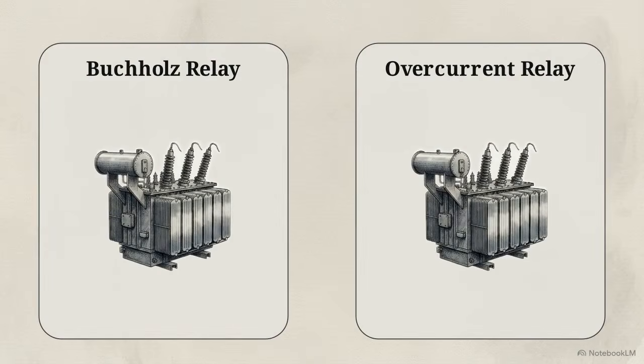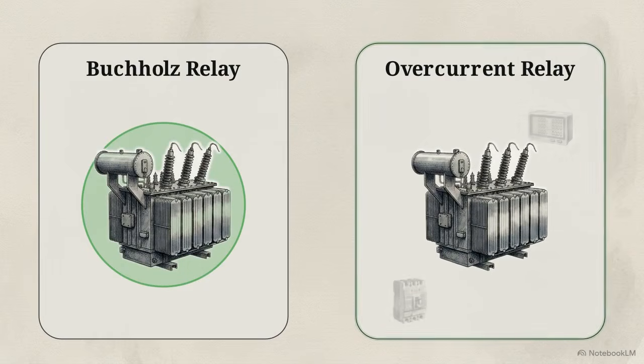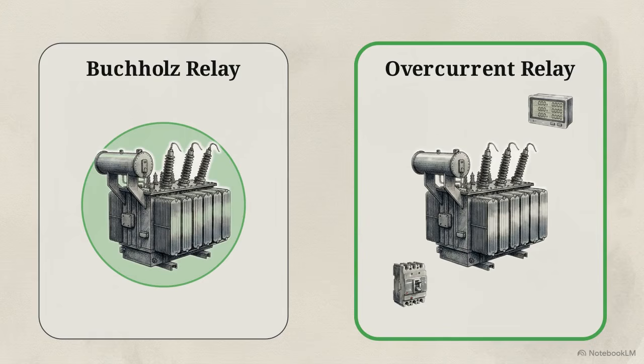This matrix compares the operational envelopes of both systems. The Buchholz relay offers high sensitivity for internal faults, while the overcurrent relay offers broad, system-wide protection with low sensitivity to internal issues. Because the overcurrent relay requires that 150% safety margin, there is a massive gap in its defense. It is mathematically blind to the low-level, smoldering internal arcs that don't immediately spike the current.